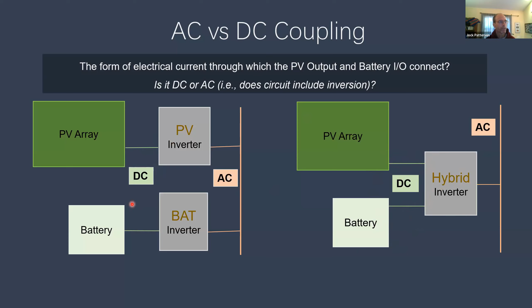And we see that the PV array's power goes through inversion to AC and then is rectified back to DC. So we have AC coupling on the left. And on the right, we have DC coupling because we never take the PV array's power, when we want to feed the battery, and go to AC. We're staying along a DC bus inside the hybrid inverter. And so that's a very efficient movement of energy. So the way we look at this, the right is a new install when you want to have a battery, an energy storage system. On the left is having an existing PV inverter and adding a battery to it. So that's the AC and DC coupling terminology.